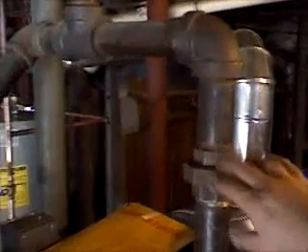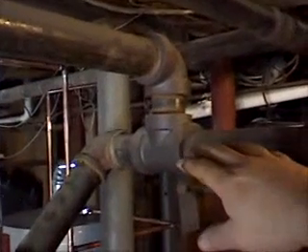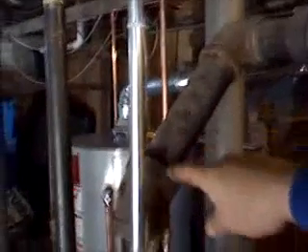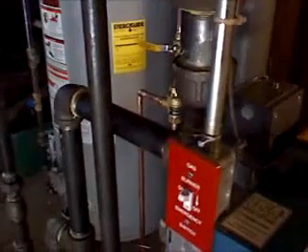Right here is where we connected to the new steam piping, and all this is the existing. This is the steam header, this part right here. And this part right here is actually what we call the equalizer. The function of the equalizer is to give the condensate return water the same pressure, so that way the boiler doesn't surge one way or the other while it's boiling.